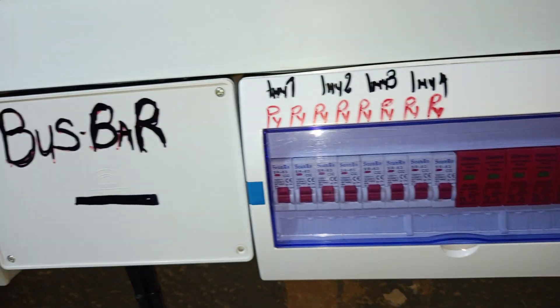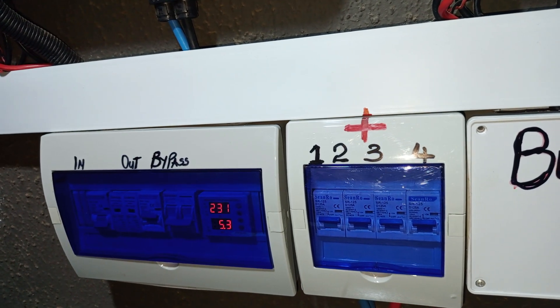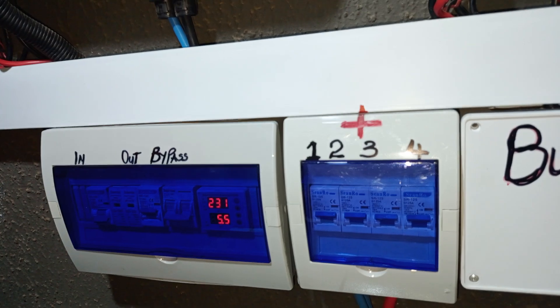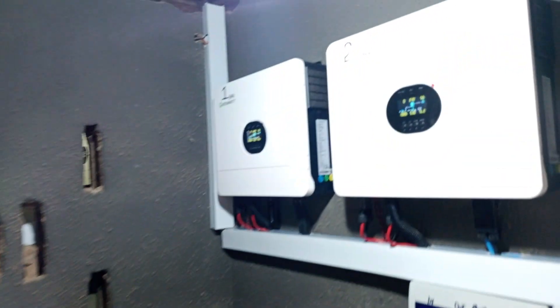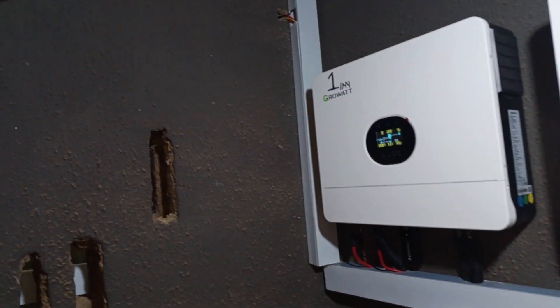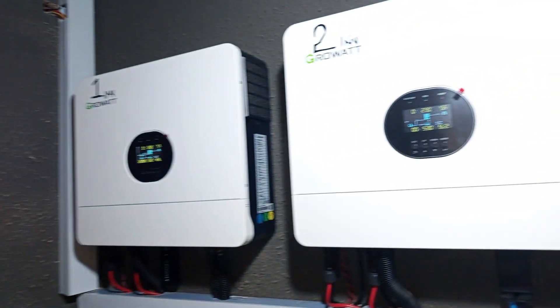What we can still do here is add more batteries if more backup is desired. Currently they have 6 ACs in this facility, but if they desire to add more load to the system, the system is robust enough to accommodate at least 3 more batteries and still run perfectly. What we have here are Growatt batteries — 15kW each. So on this side we have 45kW and on the other side we have 30kW as well.